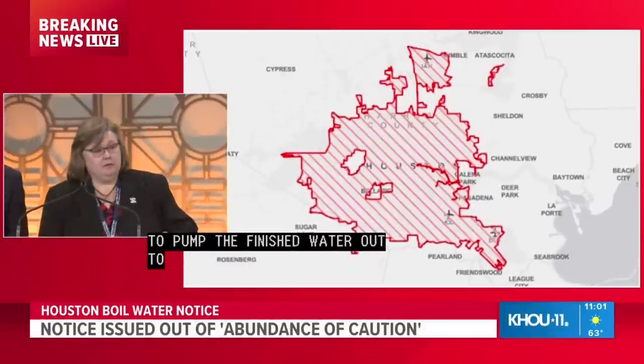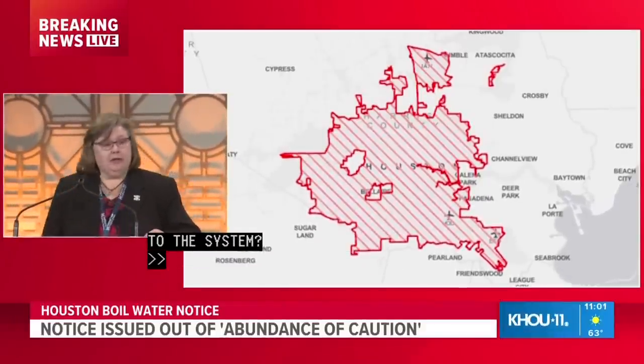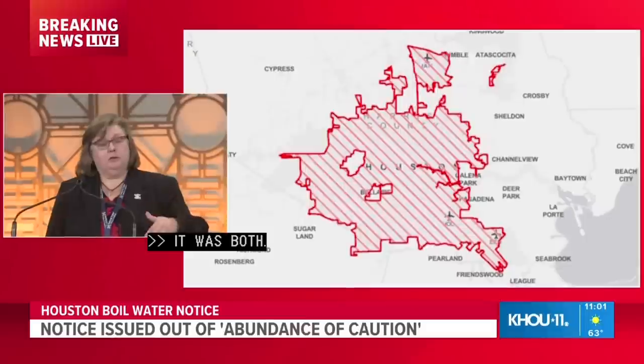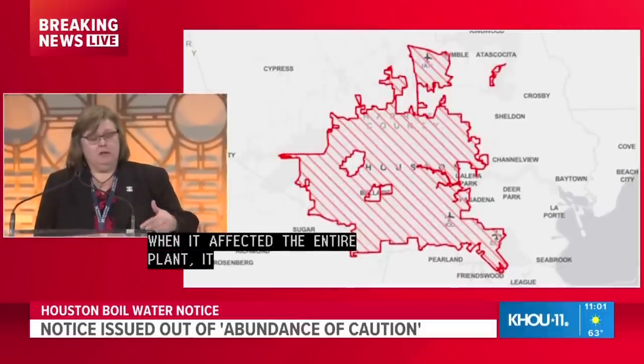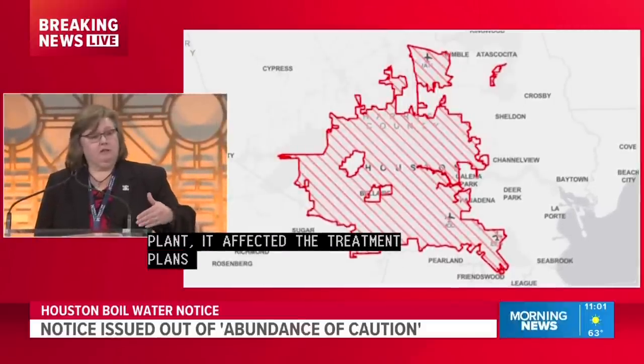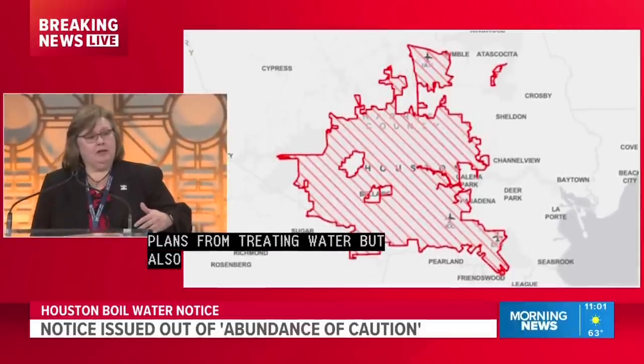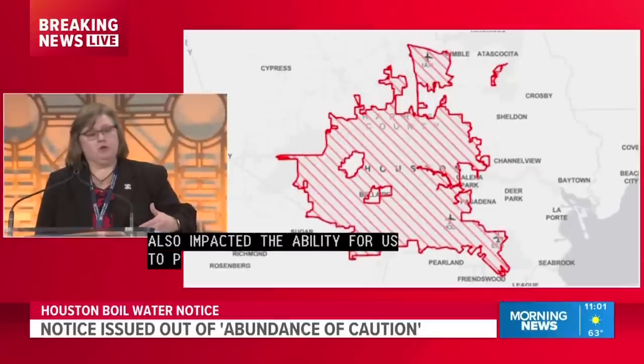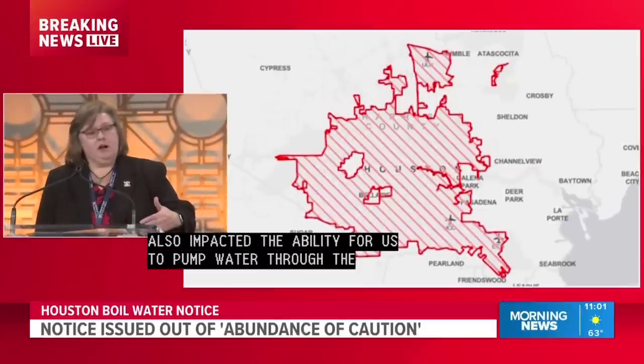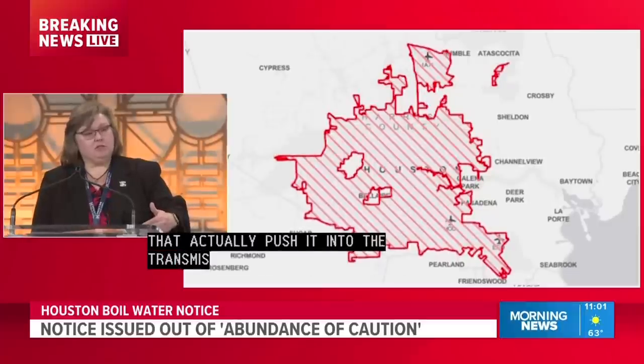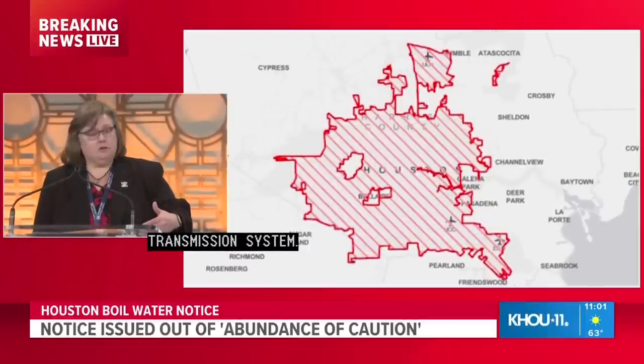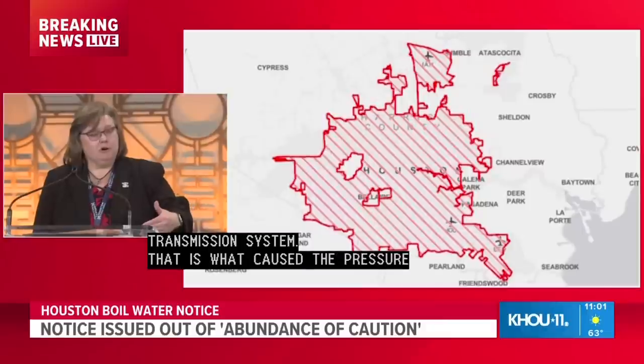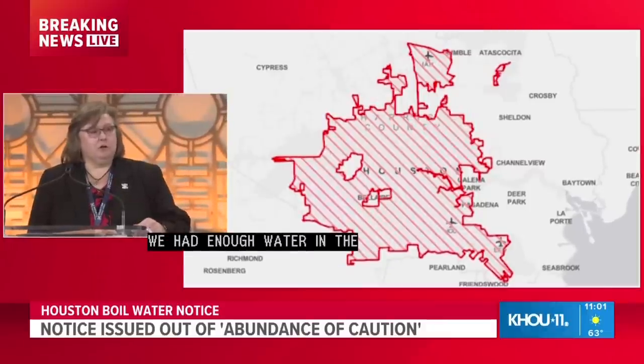So it was both. When it affected the entire plant, it affected the treatment plant's ability to treat water, but it also impacted our ability to pump water through the pumps that push it into the transmission system. That's actually what caused the pressure loss. We had enough water in the ground storage tanks—it was pushing the water into the system that resulted in the pressure loss.